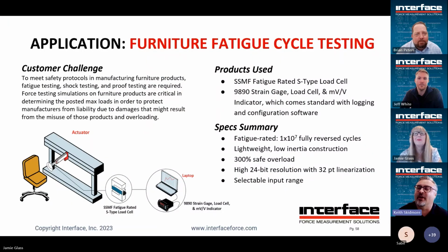Yeah, I was going to say, depending on what is intended by that question, if you take a load cell into its safe overload zone, but are using it within its capacity, it'll definitely meet spec until you start to damage it. So over repeated excursions into the safe overload territory, you may start to impact the specifications or the performance, but it doesn't necessarily meet published spec if you say we're to calibrate it up to 150% or 140%. So if you're using it up in that range, you're not necessarily within published specifications. All right, it's probably not 10 times worse, but somewhat worse.